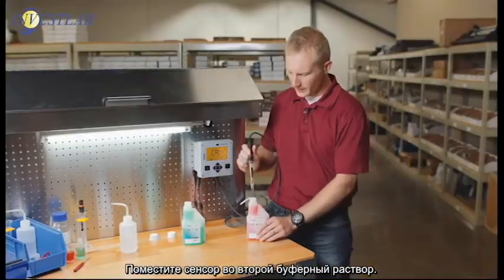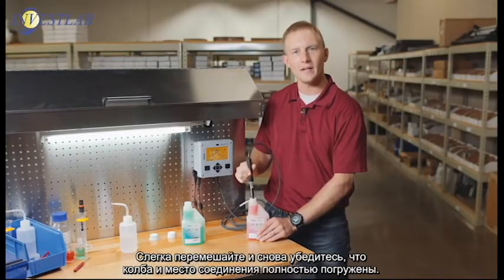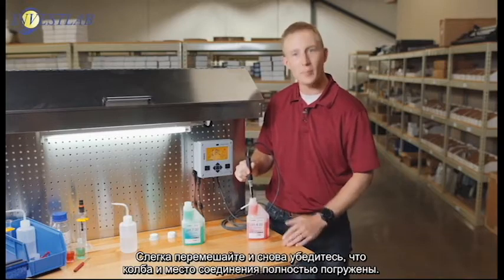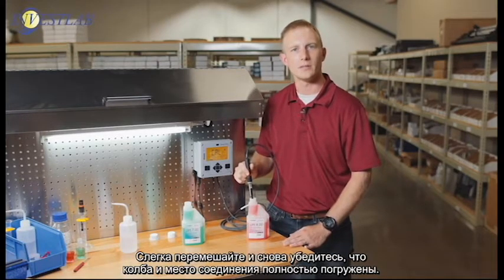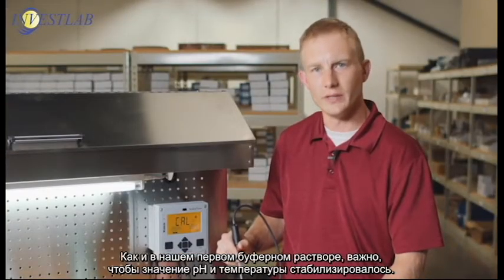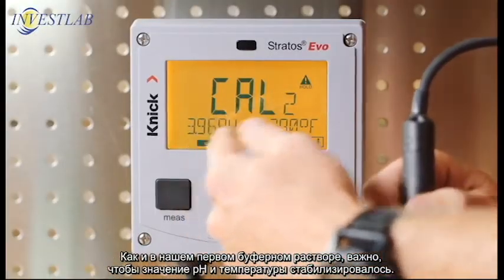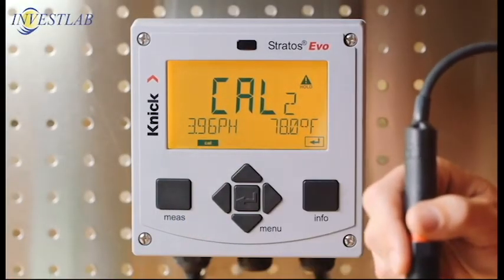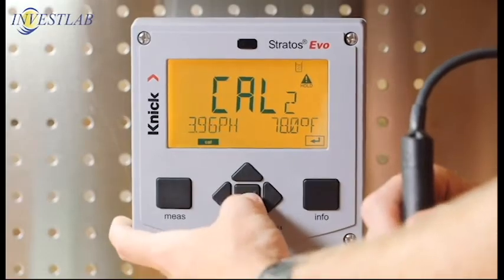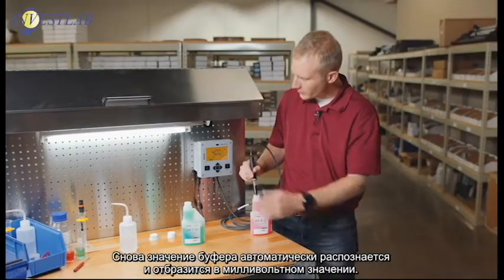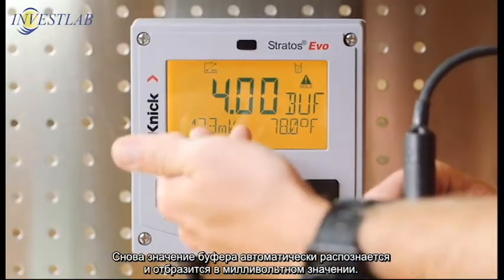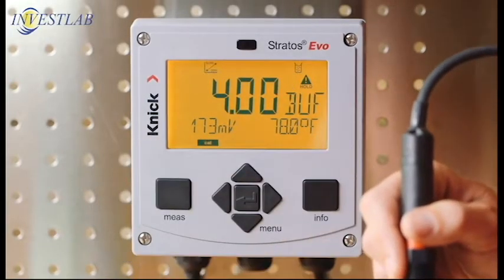Place the sensor in the second buffer solution, stir lightly, and again ensure that the bulb and the junction are completely immersed. Just like in our first buffer solution, it's important to let both the pH and temperature value stabilize. We'll then press enter. Again, the buffer value is automatically recognized and our millivolt value is also displayed.